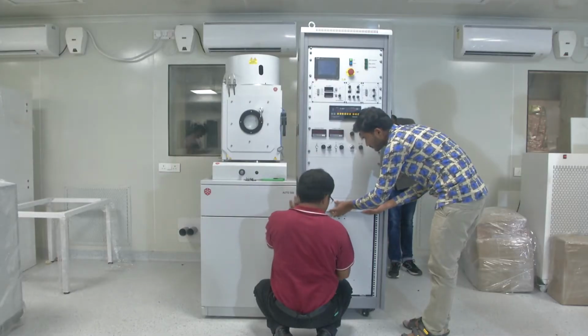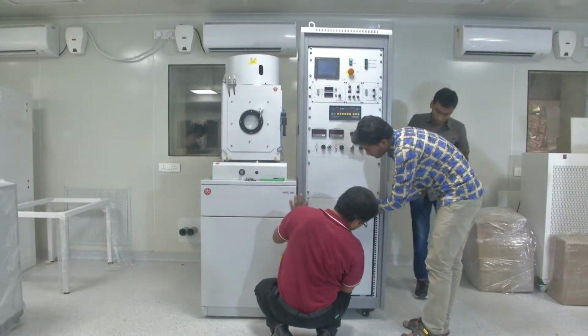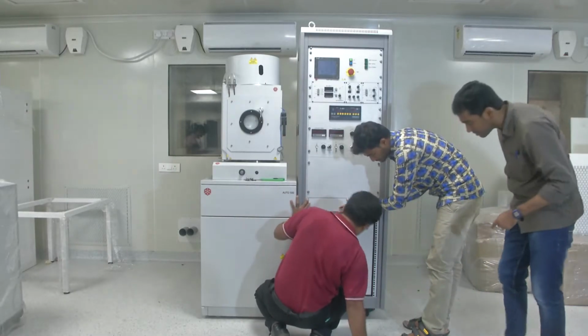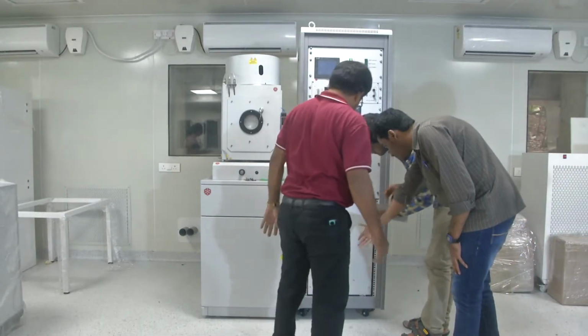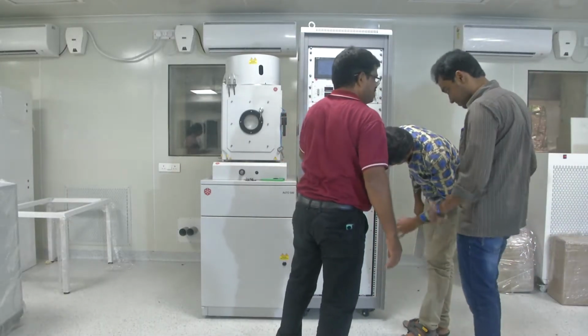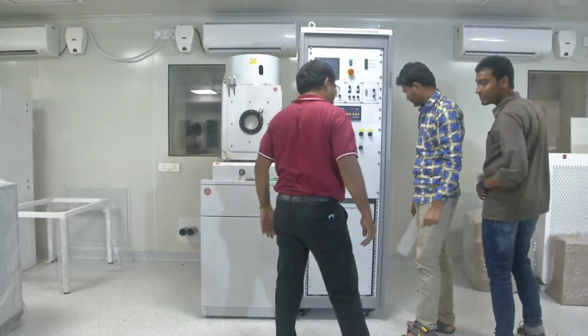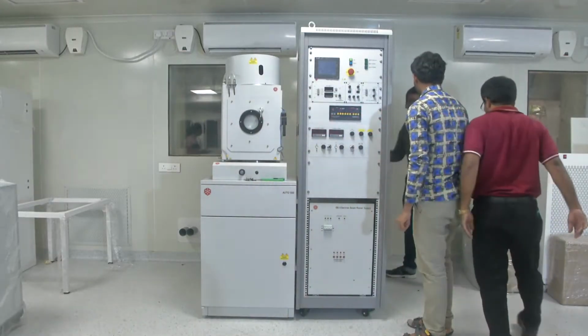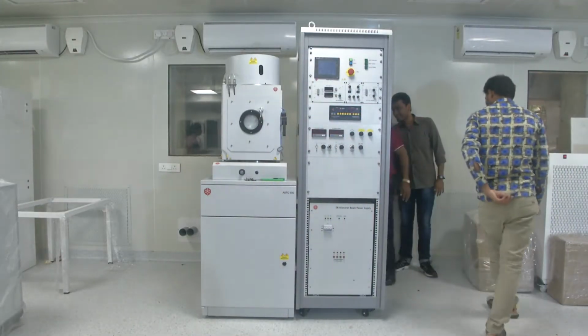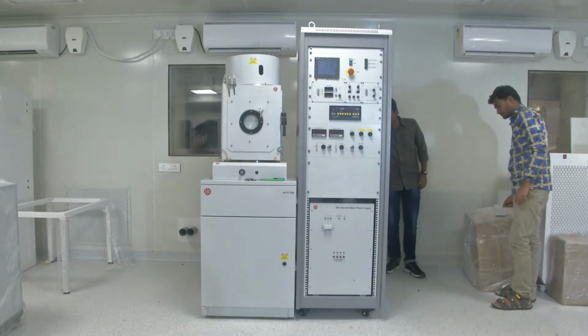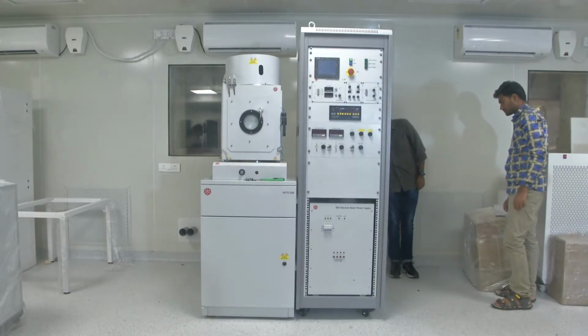Now, we have finally pushed the power supply into the control panel housing. Now, we will make the connections from behind. We have made 3-phase connections with a good ampere rating for this power supply unit. And this power supply unit will power the control panel. Separately on the left side, you can see the chamber. The chamber will have its own separate power supply that will be supplied through a dedicated connection.